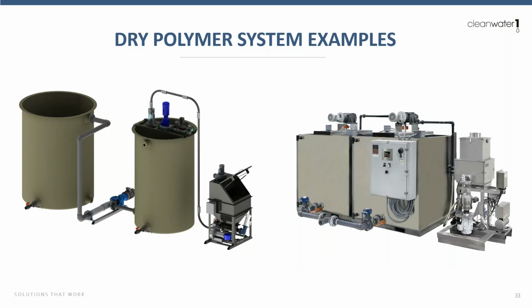On the left side there, what we have is called a shower type wetting head. This system uses pneumatic conveyance to blow or convey the polymer up to that tank top wetting head. In that wetting head, there are spray jets that are spraying a 360-degree pattern, and that polymer is wetted as it's dropping down into the mix tank. The system on the right is what we would call a mechanical mixing bowl assembly. In this system, the volumetric feeder feeds directly out of the hopper into the wetting bowl assembly. Within that wetting bowl assembly, there's a cyclone of water, and then there's also an impeller in there to help create high energy mixing. The different types of systems require different types of maintenance and different types of cleaning.